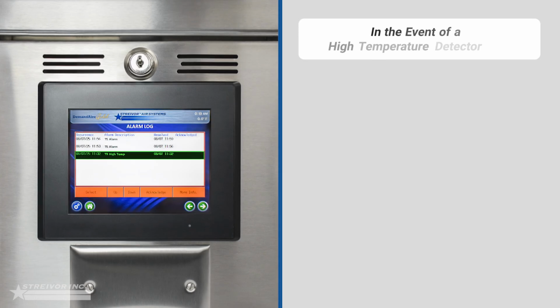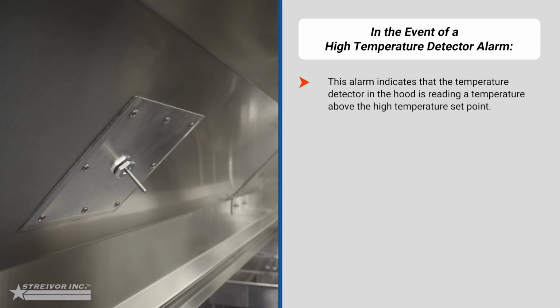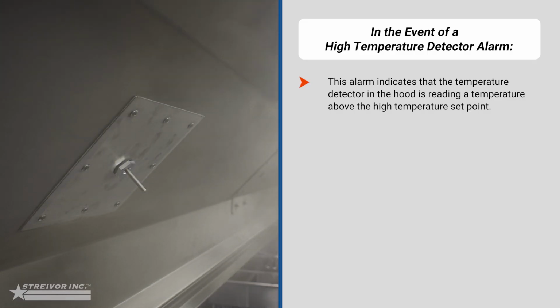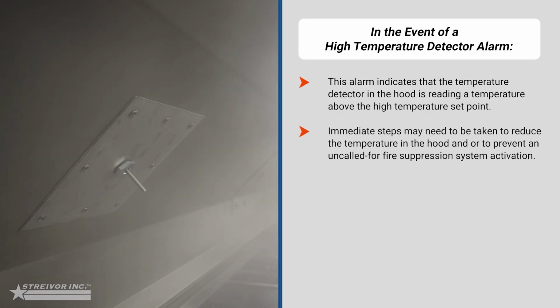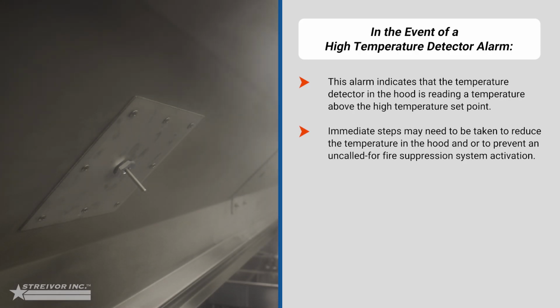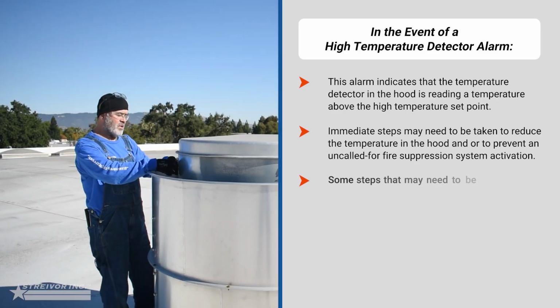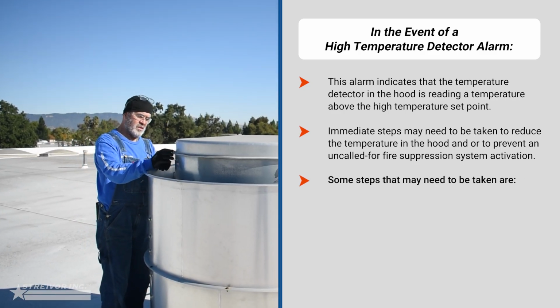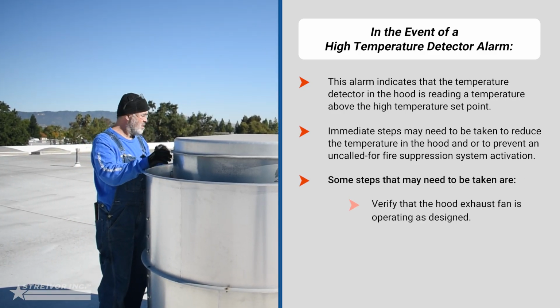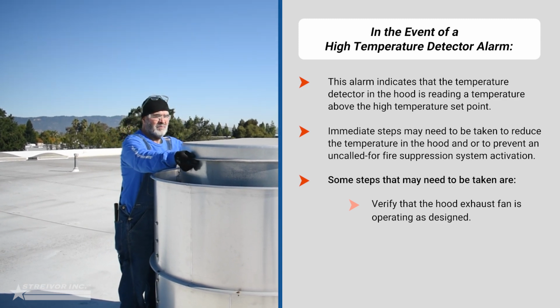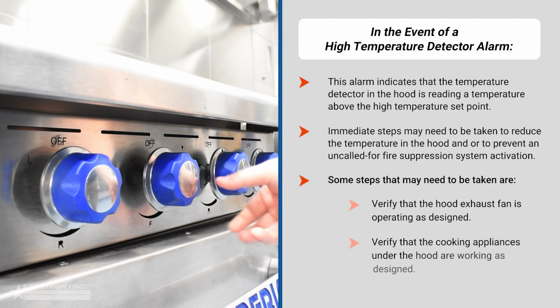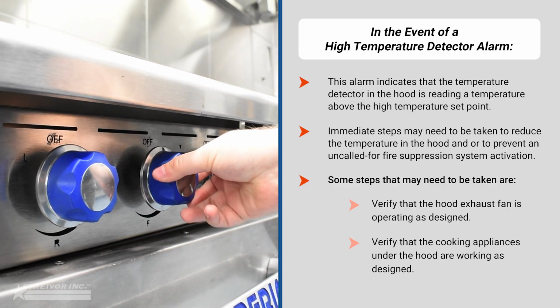In the event of a high temperature detector alarm, this alarm indicates that the temperature detector in the hood is reading a temperature above the high temperature set point. Immediate steps may need to be taken to reduce the temperature in the hood or to prevent an uncalled for fire suppression system activation. Some steps that may need to be taken are: verify that the hood exhaust fan is operating as designed. Verify that the cooking appliances under the hood are working as designed.